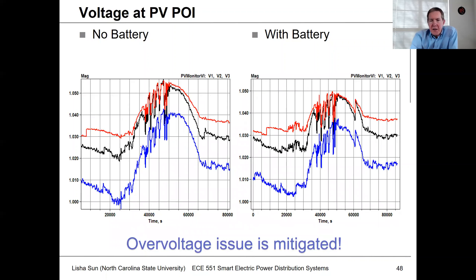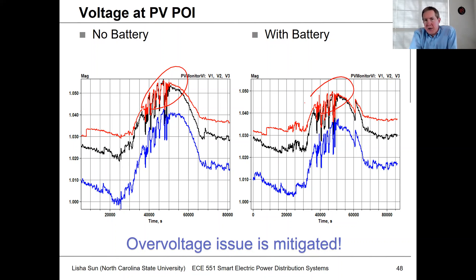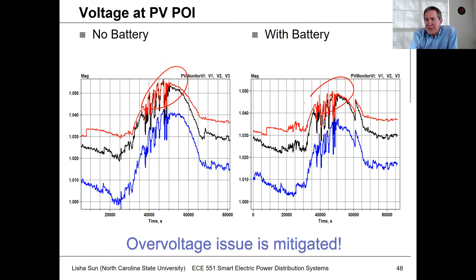This shows that without the battery, you get overvoltages. When you have the battery charging during peak PV times, it helps keep voltages down. This is kind of an expensive solution, though.